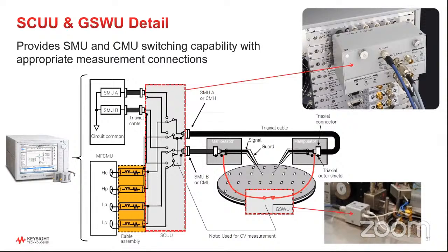One other quick comment before I leave. That picture in the upper right showing the SCUU connected directly to the output of the instrument is not the way you'd really want to use it in practice. We actually have an extension cable that can go a couple of meters at least beyond that. So what we normally do is you connect this extension cable to the instrument, and then the extension cable connects to the SCUU, and you mount the SCUU on your wafer prober or whatever you're probing, because you really want to keep the cables short. The meter will compensate automatically for that extension cable. And that means that the only thing you actually have to do compensation, like open short calibration on, is whatever additional cables you've added beyond the SCUU. And I'll show you a picture on a wafer prober later how that actually works.